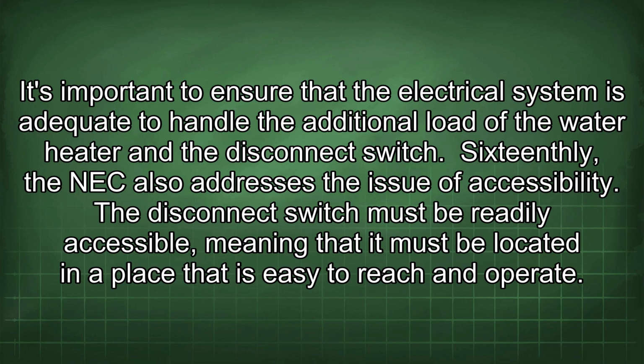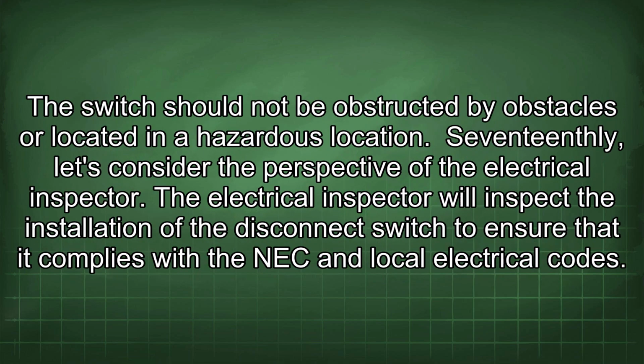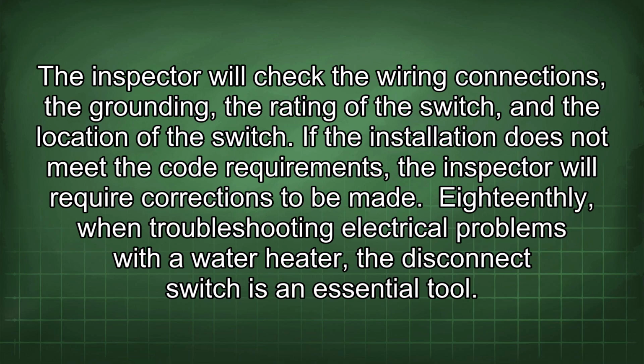The disconnect switch must be readily accessible, meaning that it must be located in a place that is easy to reach and operate. The switch should not be obstructed by obstacles or located in a hazardous location. 17th, let's consider the perspective of the electrical inspector. The electrical inspector will inspect the installation of the disconnect switch to ensure that it complies with the NEC and local electrical codes. The inspector will check the wiring connections, the grounding, the rating of the switch, and the location of the switch. If the installation does not meet the code requirements, the inspector will require corrections to be made.